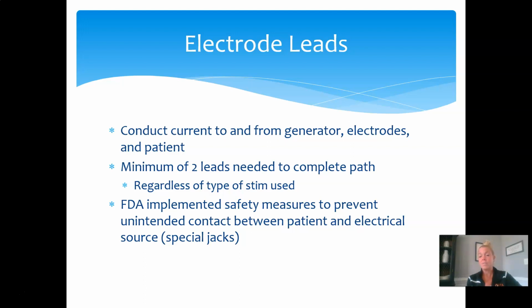The units themselves are going to shape the electricity into certain waveforms that are more tolerable by the body. So we have a couple safeguards in place. Plus, our machines are inspected on an annual basis, and that is probably the biggest thing they're actually looking for, is that are the machines safe, that they're carrying electricity the way that they should, and they're not going to cause harm to anyone.